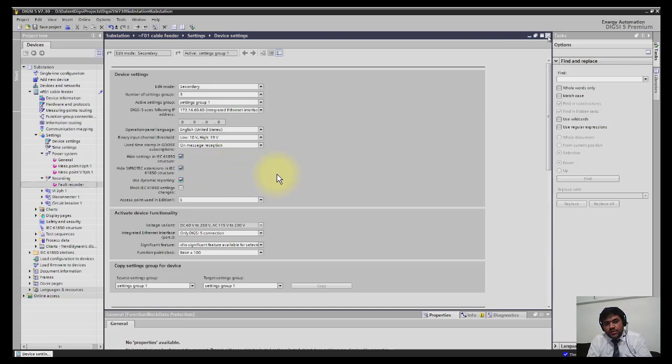You have the option of sampling frequency from 1 to 8 kilohertz. The device can store up to 120 fault records. When a new fault record comes, it will delete the oldest fault record. The fault record also has a duration—for example, it could be 1200 seconds if you select 1 kilohertz sampling. If you select high sampling rate, the duration will come down but the quality will improve.